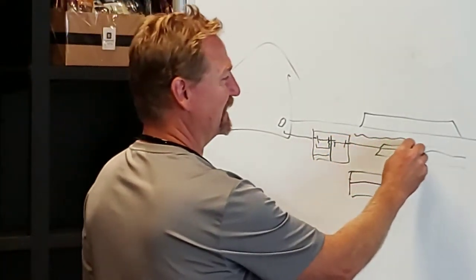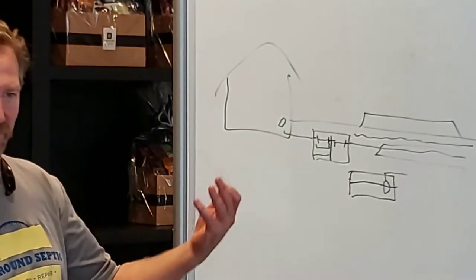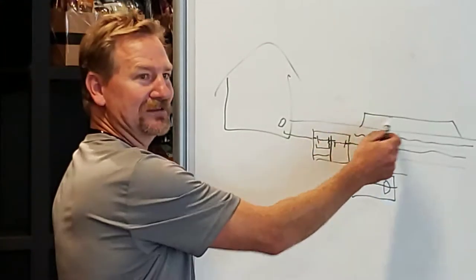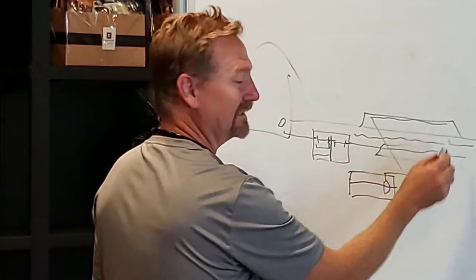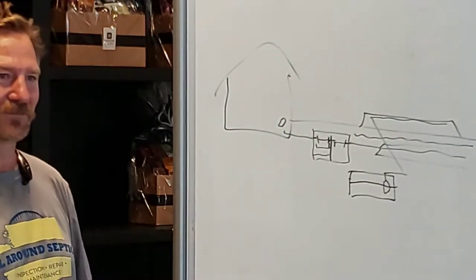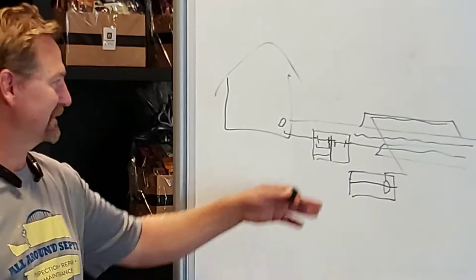If it's all clay, where do you put the drain field? There are a couple of different ways. You'll see a mound in the front yard. The clay layer may be right there, so a gravity system won't give three feet of separation before the liquid is clean. You need three feet of sand for the liquid to run through and clean. So we create three feet by building a mound up, and we put the drain field on top of the mound, feeding it at a controlled rate.